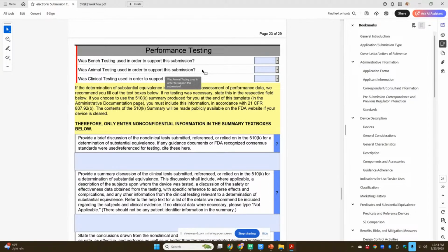Some things you can't demonstrate on a sawbones model. For a bone void filler product, I have to show that it actually integrates, through osteoconduction or osteoinduction, with the bone. And that requires time. So you have to actually damage the animal's bone, put the bone void filler in there, sew up the animal, and let them live with that and heal. And then you euthanize the animal and study whether that bone void filler integrated with the bone. Whenever we can, we try to eliminate these studies however we can. But some things can only be tested one way, unfortunately.